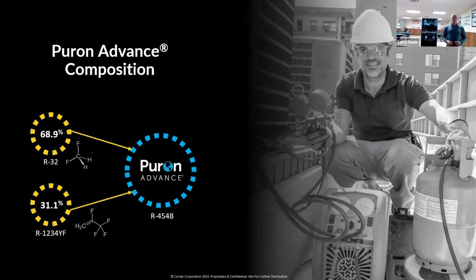So what is in 454B? There's been a lot of miscommunication, misunderstanding. In fact, I thought the wrong thing for a while. Hey, this is a flammable refrigerant. It has propane in it. That is not the case. 454B contains about 69% of R32, but it's blended with R1234YF at about 31%. And that creates the 454B. So it has a low flammability. It is just above that non-flammable threshold.